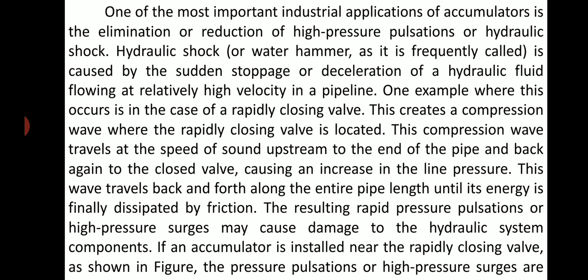This creates a compression wave where the rapidly closing valve is located. This compression wave travels at the speed of sound upstream to the end of the pipe and back again to the closed valve, causing an increase in the line pressure. This wave travels back and forth along the entire pipe length until its energy is finally dissipated by friction. The resulting rapid pressure pulsations or high pressure surges may cause damage to the hydraulic system components.